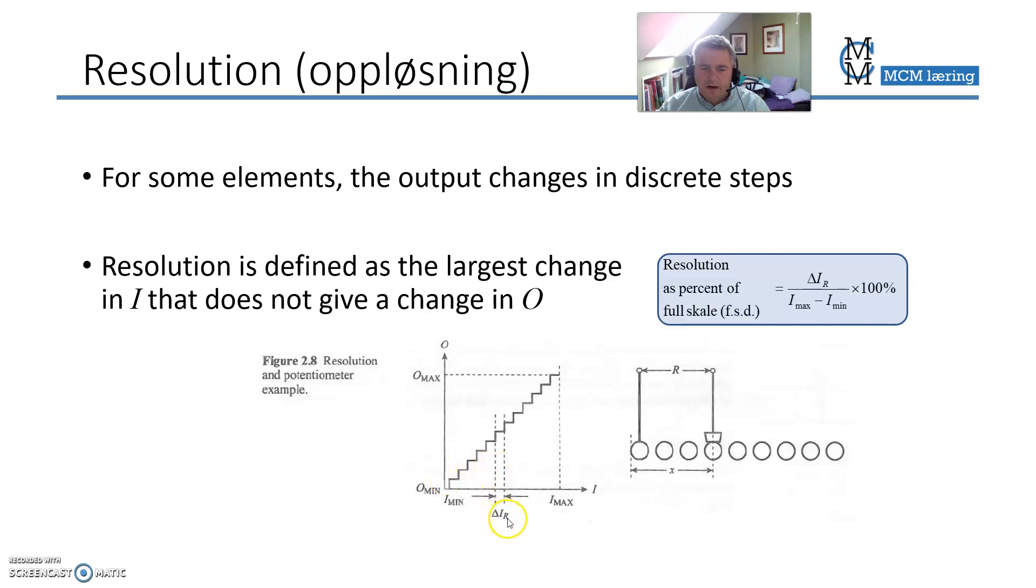So resolution is defined as the largest input you can do without a change in the output. So here is Delta I_R input resolution. You can actually go from here to this dotted line all the way to here without a change in the output. Ideally, this ideal Delta I_R should be as small as possible. That would mean that you have a high resolution. You have a lot of steps on the way up here, so the line becomes almost as a continuous line without the steps if the steps are small enough.